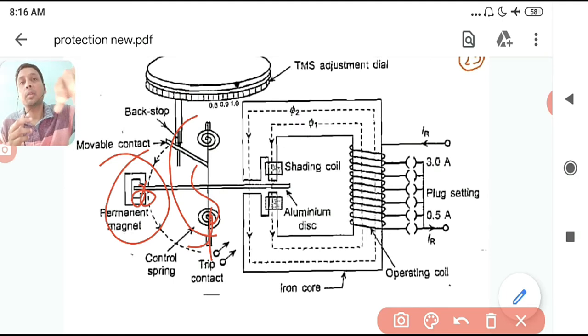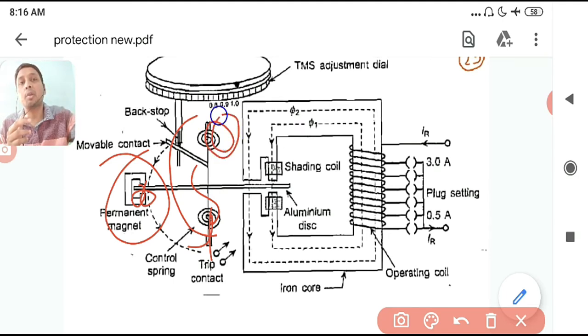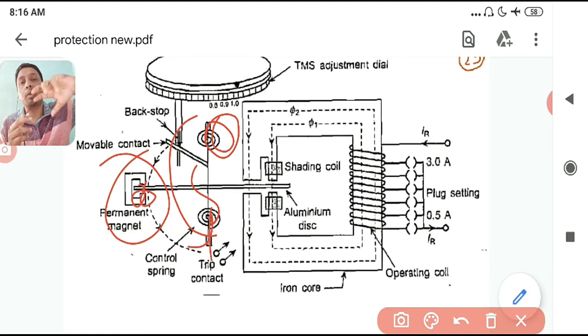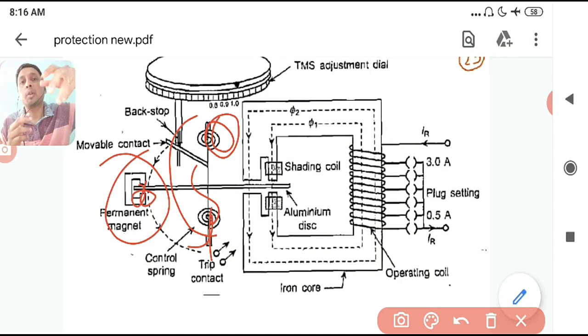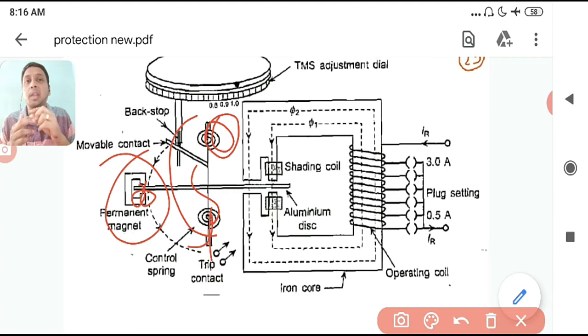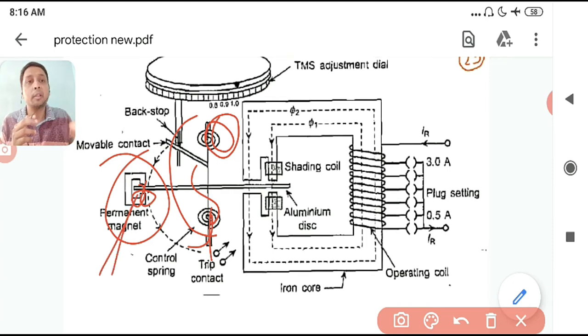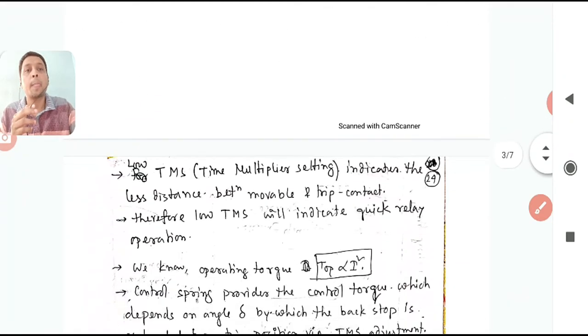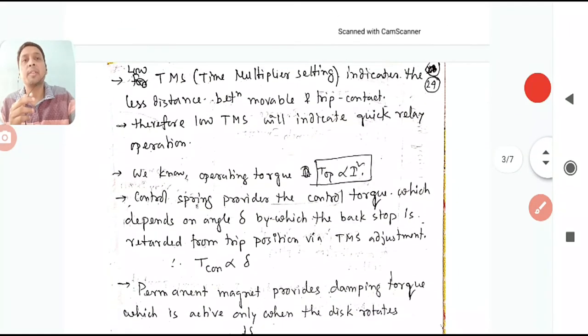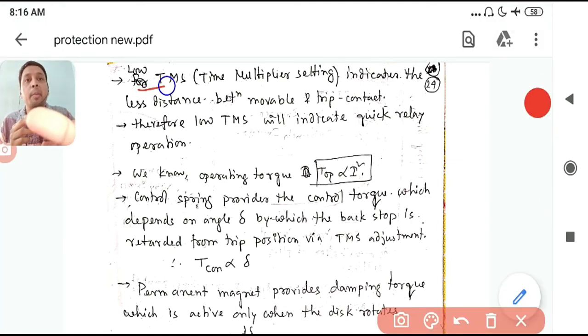The angle θ represents how far the disc is from the trip contact. The control spring torque depends on θ — full rotation compresses the spring more, giving more control torque. Control torque is directly proportional to θ, and damping torque is directly proportional to dθ/dt. We will now try to derive the relation for operating time.